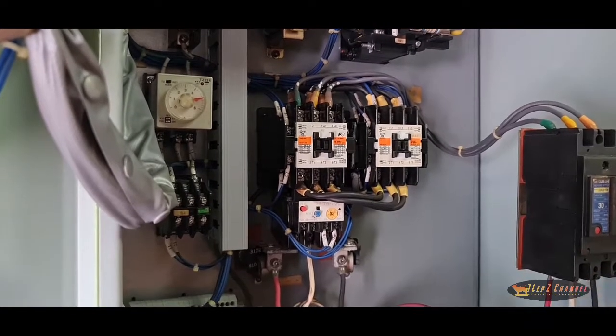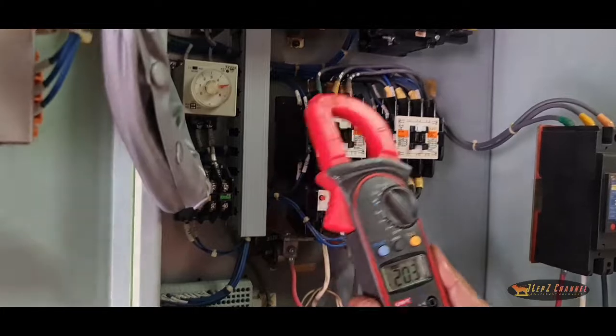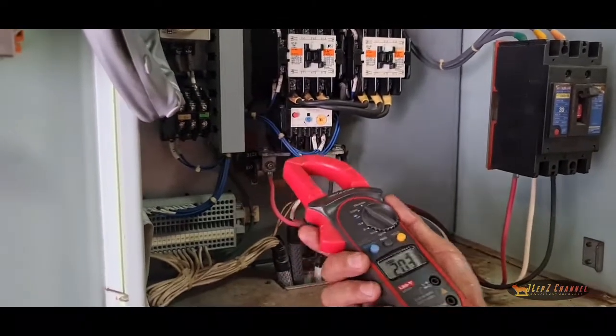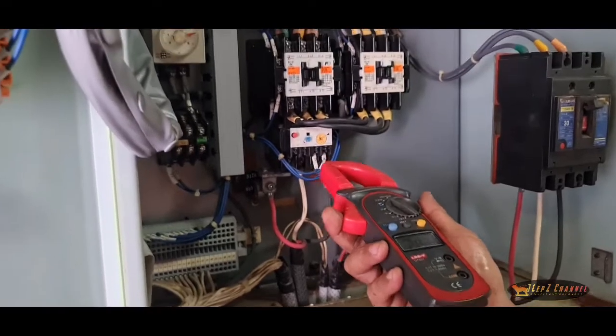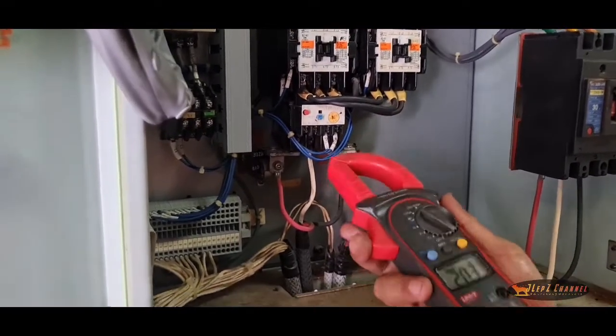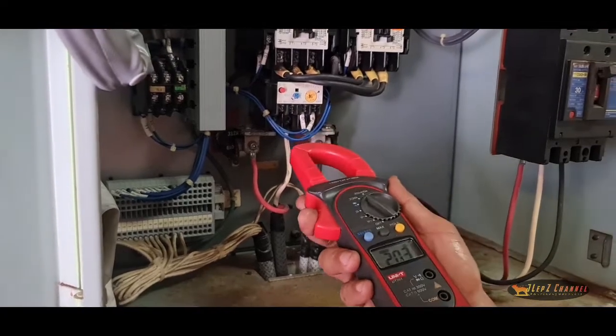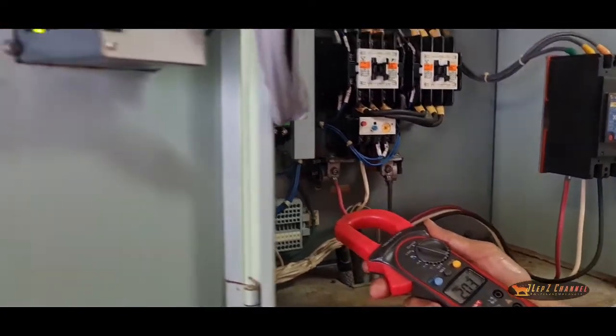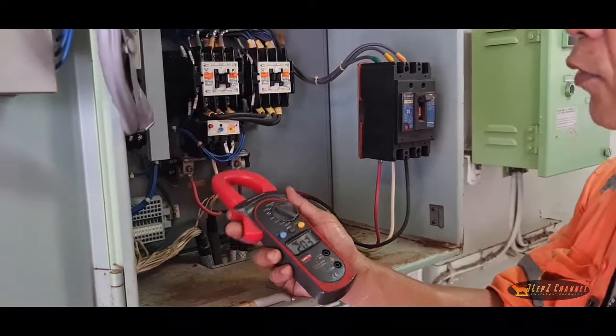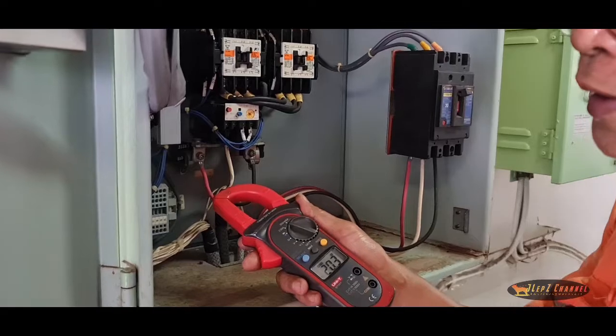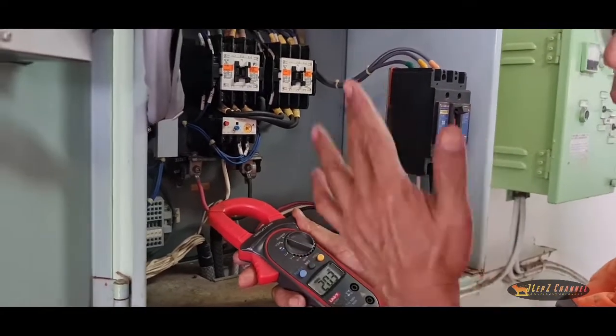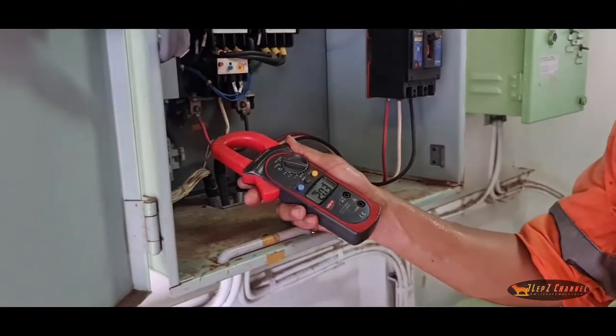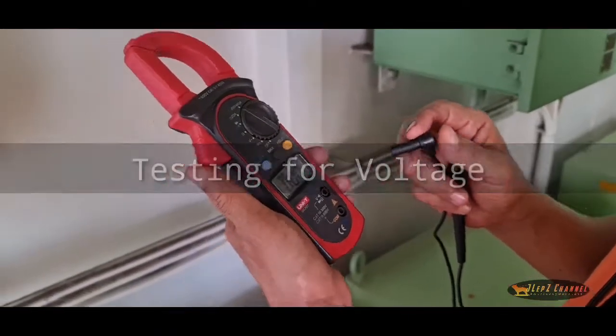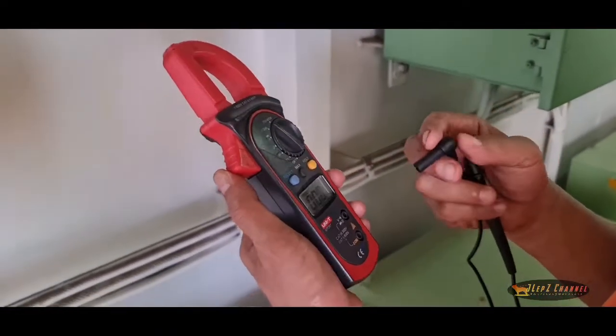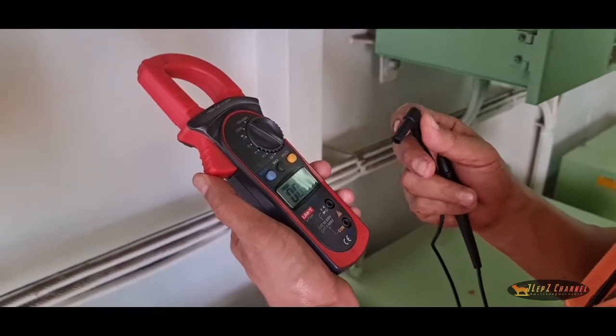So that's it. Our topic is how the use of the clampmeter is useful in setting the overload relay to a safe maximum current. The maximum is 29, but we set it here at only 26, so that it stays below the average, at the safest value for setting the overload relay. This clampmeter is not only for that. It is a versatile tool, a flexible tool.